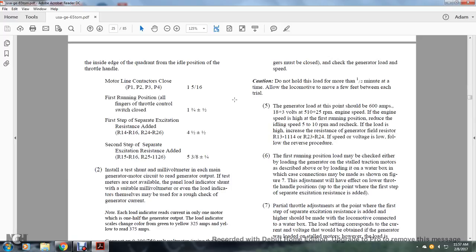The inside of the quadrant shows the following throttle handle positions: idle position — motor line contactors P1, P2, P3, P4 close at 1-5/16 inches; first running position — all throttle control switches close at 1-3/4 inches plus or minus 1/2 inch; first step — excitation resistance added to R14, R16, R24, R26 at 4-1/2 plus or minus 1/2 inch; second step — separate excitation resistance added to R15, R16, R25, R26 at 5-3/8 plus or minus 1/4 inch. Install test shunt millivoltmeter on each generator to read generator output current. Panel motor load indicators may also be used for a rough check of generator current.